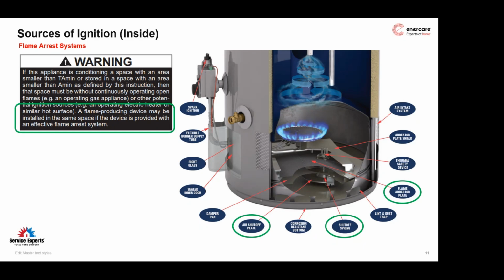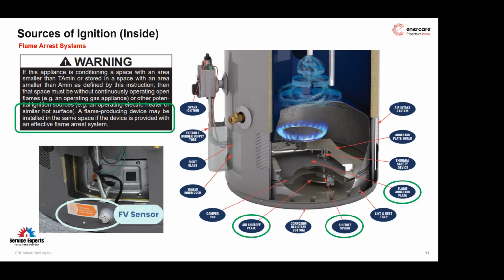This thing's in my way. Wish I had a different screen. Right here, if you look at this, that is the TRD, or thermal relief device, that will break if it's overheated, causing that spring-loaded door to close and prevent any air from entering the combustion chamber below. Now, if I could just get this to move forward, everything would be fine. There we go. Most water heater manufacturers will utilize a flammable vapor sensor, like the one pictured on the bottom left, combined with an arrestor plate or an arrestor screen that also meets this standard we're talking about, an effective flame arrest system.